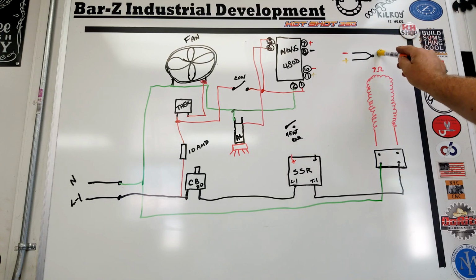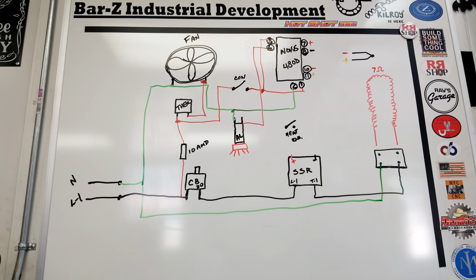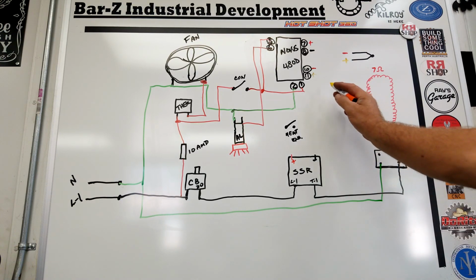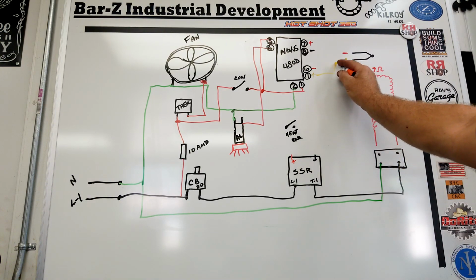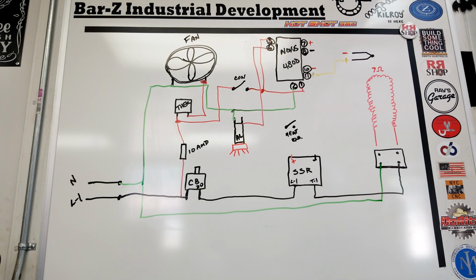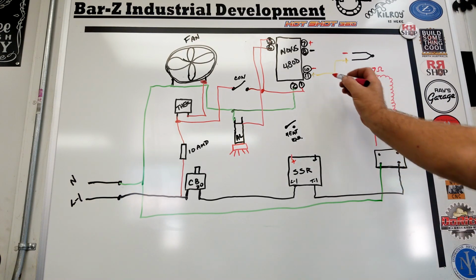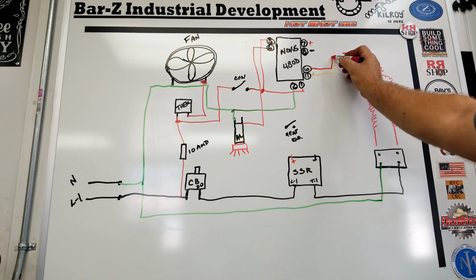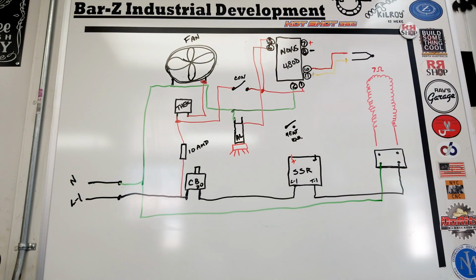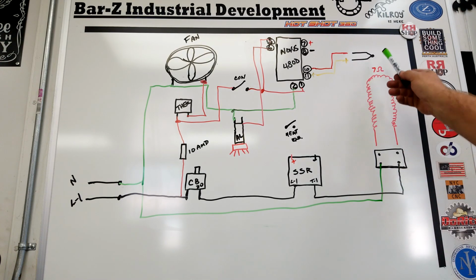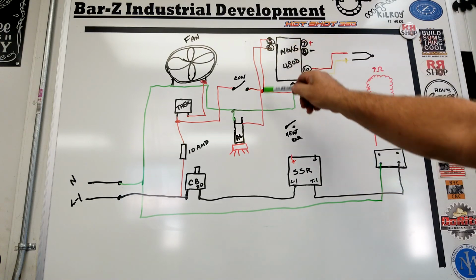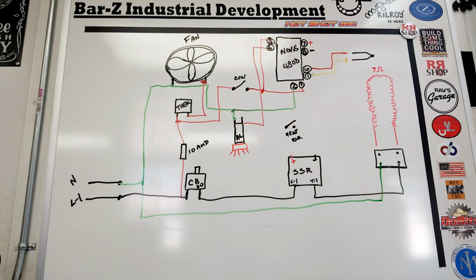We need to hook up this thermostat within the unit. There's a small thermostatic probe that's on your list. And make sure you use type K thermocouple wire. It's color coded yellow and red. So we're going to code those in yellow and red. And red is negative, by the way, on that stuff. So keep that in mind. It's real easy to get those switched up. Okay, so we've got temperature sensing. We've got alarm. We've got power. All we need to do now is get this SSR working and get us a pulse output.